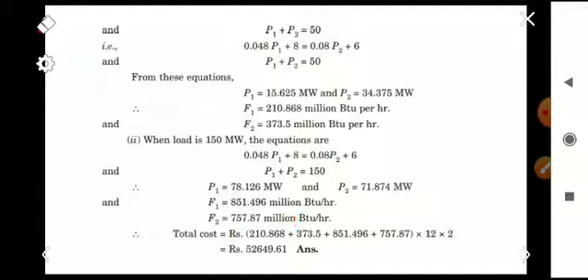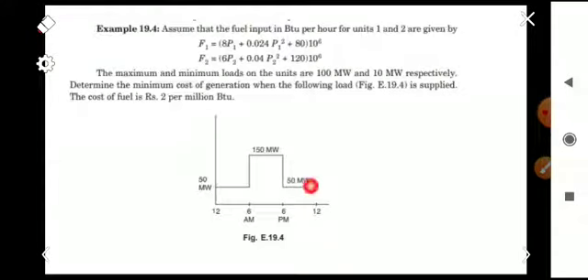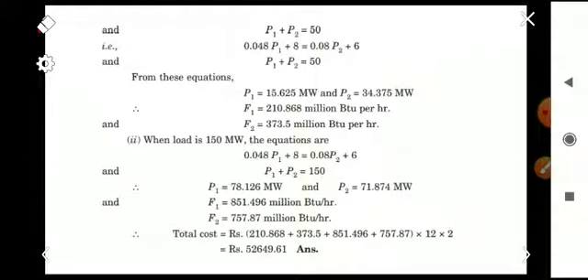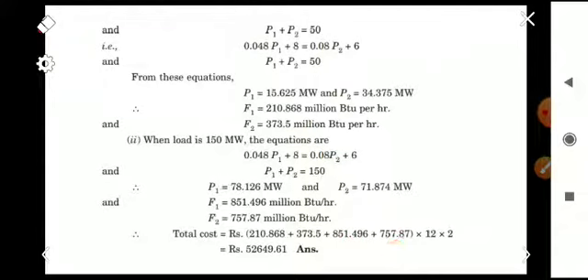For the third case — 6 pm to 12 am — the total consumption is again 50 megawatt, same as the first period. So for 6 + 6 = 12 hours, the load is 50 megawatt, and for another 12 hours, the load is 150 megawatt. We find the total cost as (F1 + F2) for 50 MW plus (F1 + F2) for 150 MW: that is 210.868 + 373.5 + 851.496 + 757.87. All these values are per hour.